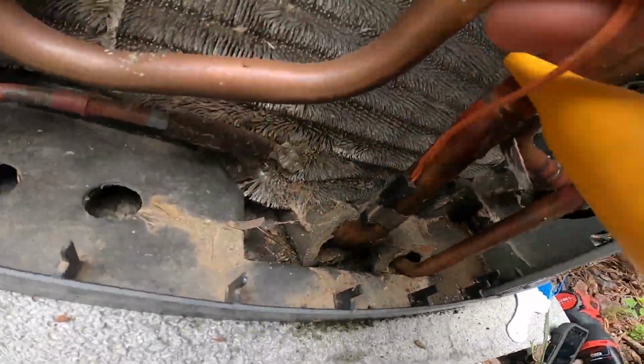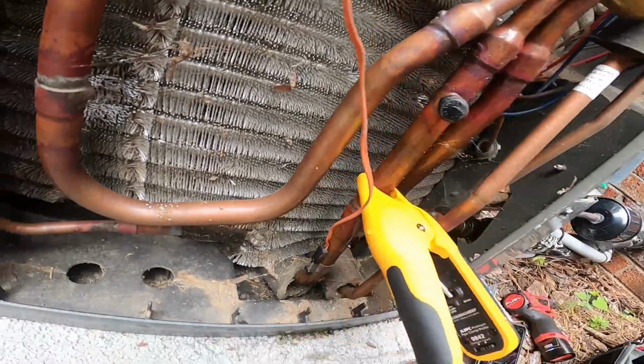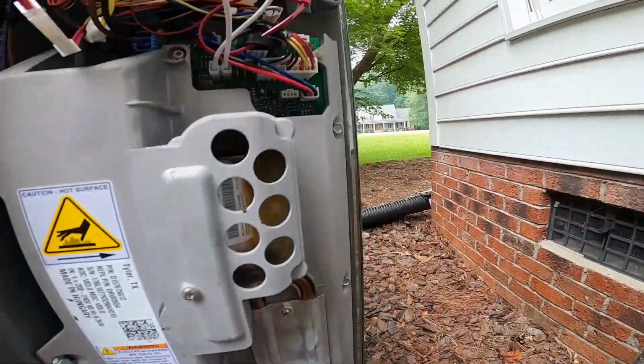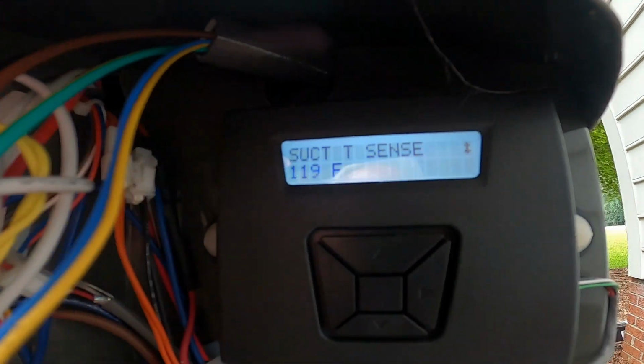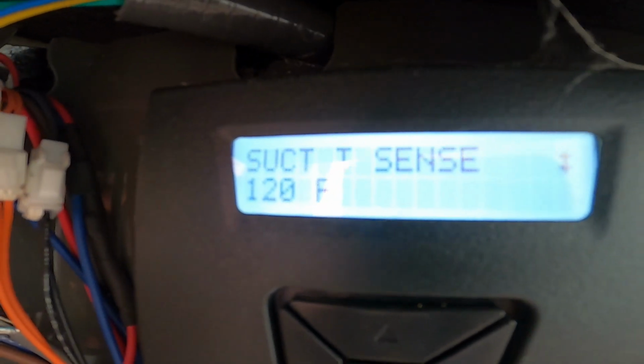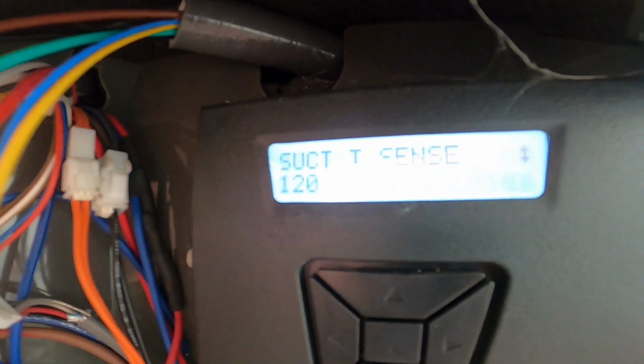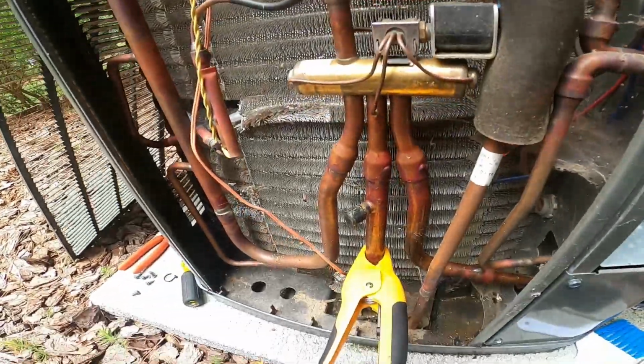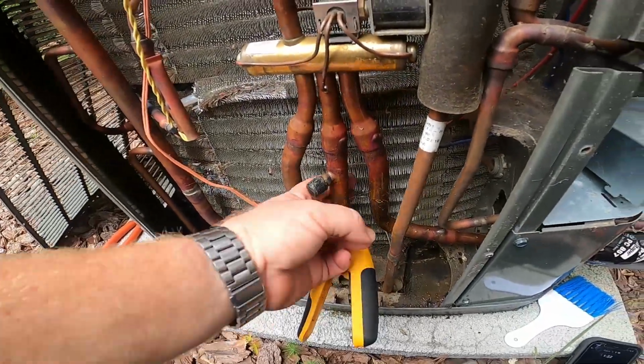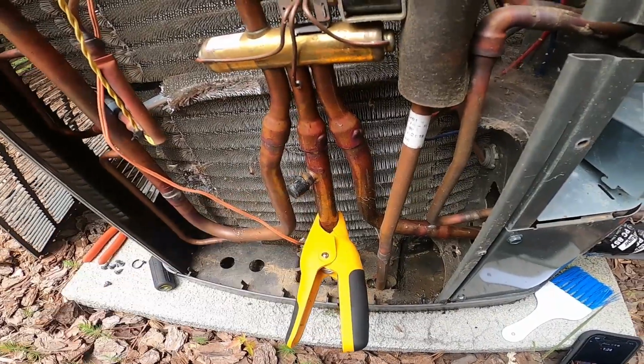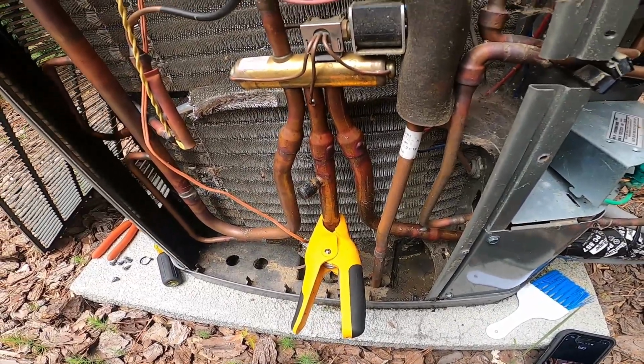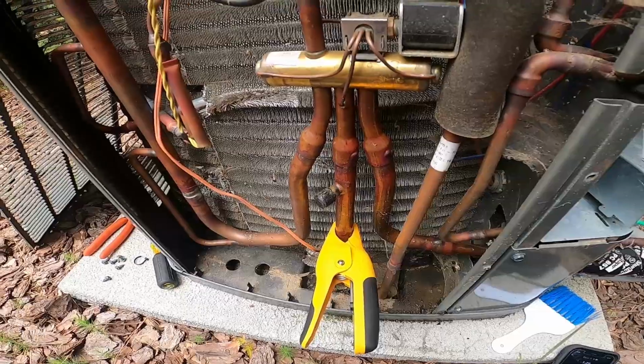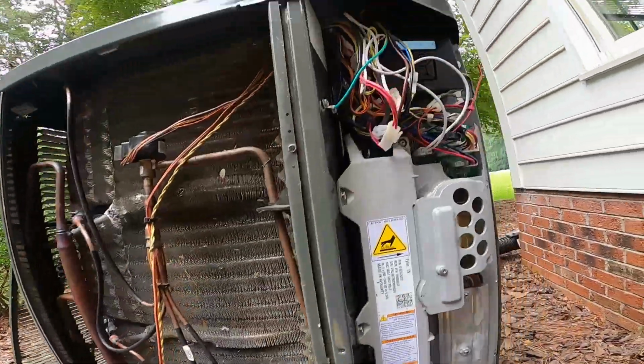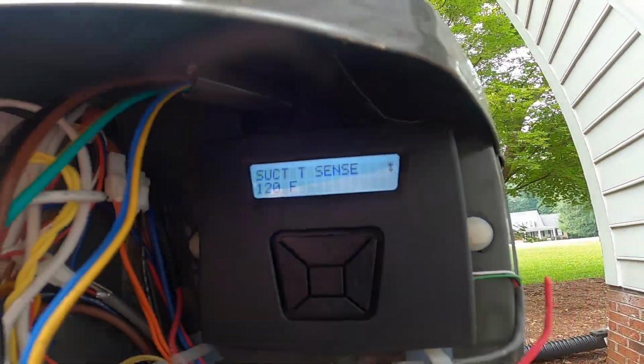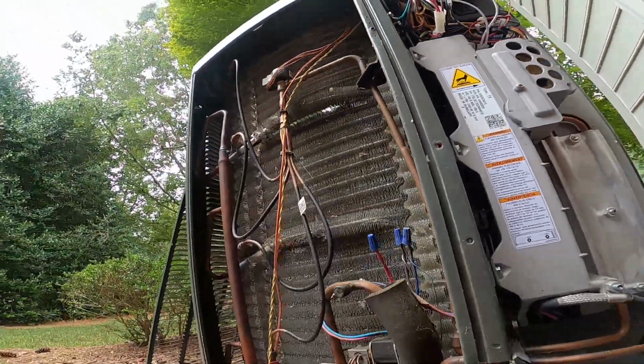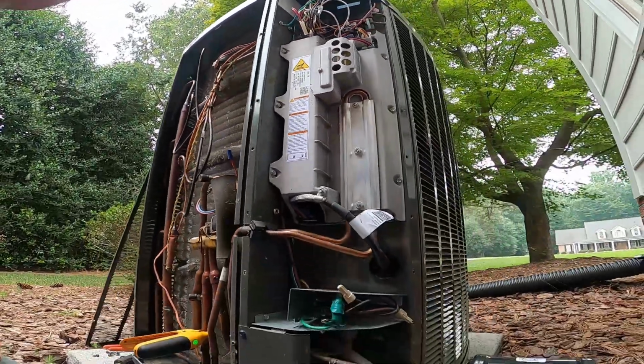Suction line temperature sensor right there on this unit. That sensor is telling me that we are reading a suction line temperature of 120 degrees. Now, call me kooky, but that line's cold and it's sweating, and I'm not seeing a problem with the refrigerant charge in this thing. We just got a sensor telling us we've got a line temperature of 120 degrees, and we are running this thing in cooling, not in heating. So.